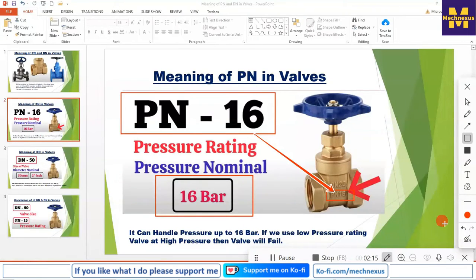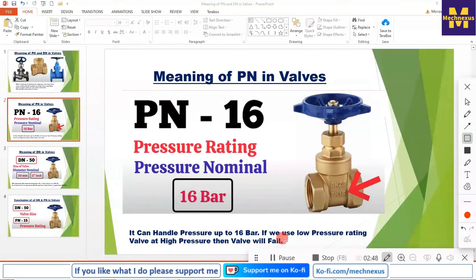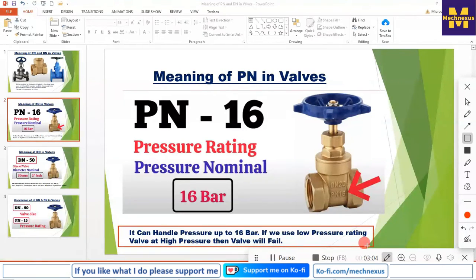While selecting a valve, it is very important to know the working pressure. If you use a low pressure valve it will fail. For example, if your working pressure is 20 bar and you have used PN 16, then it will fail. Also, never use an unnecessarily higher rated valve — if your working pressure is 20 bar and you are using PN 30, 40 or higher, that is a wastage of money. It is recommended to use the right pressure number for your valve.